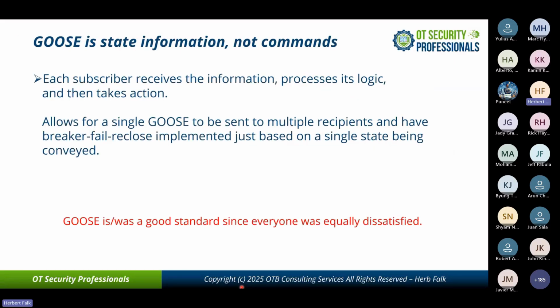Okay, GOOSE is state information and not commands. So that's something a lot of people have to get their head around. Each subscriber receives the information, processes that information in its logic, and then takes action. And this allows for a single GOOSE to be sent to multiple recipients and have something like breaker fail reclose implemented with just a single state being conveyed. I always like to say a good standard is one in which everyone is equally dissatisfied, and GOOSE was a good standard by that definition.